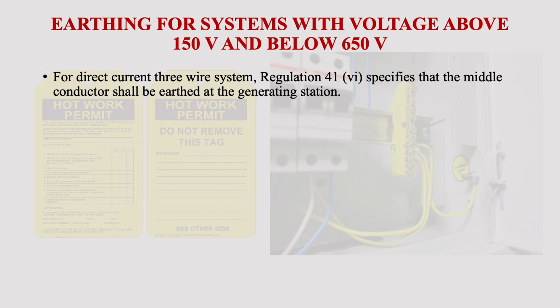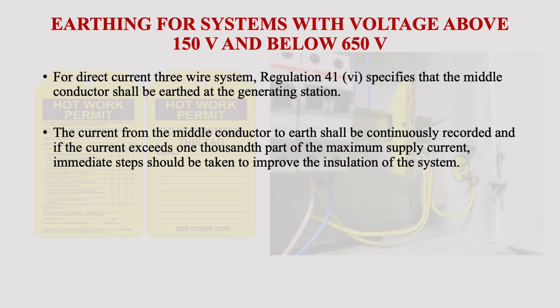So you should understand that we are focusing our discussion only on the applicable regulations and not on the technical know-how of how the earthing system is to be carried out. For the direct current 3-wire system, regulation 41(vi) specifies that the middle conductor shall be earthed at the generating station only, and the current from the middle conductor to earth shall be continuously recorded by means of a recording ammeter. And if at any time the current exceeds 1/1000 part of the maximum supply current, immediate steps should be taken to improve the insulation of the system.